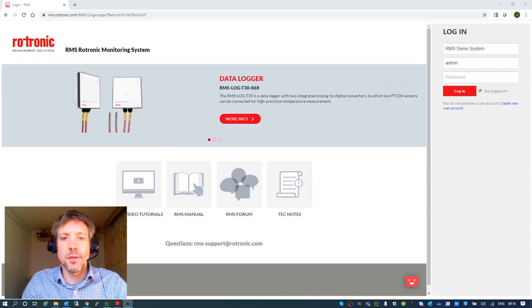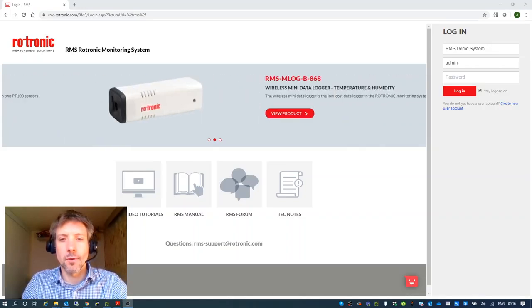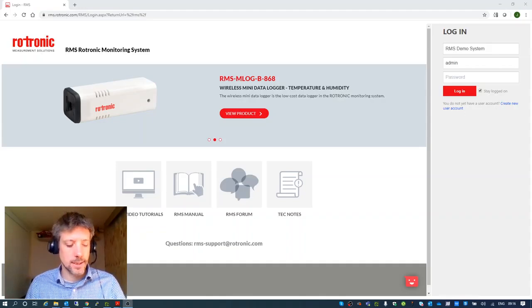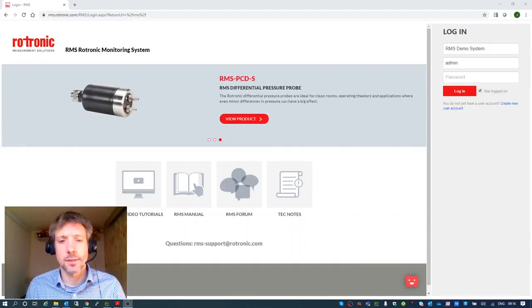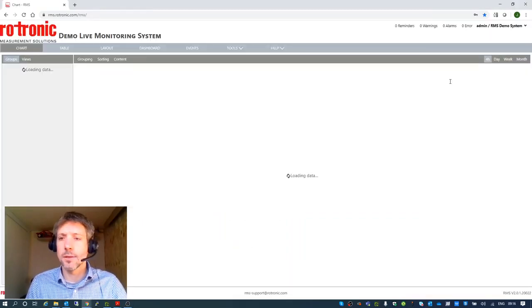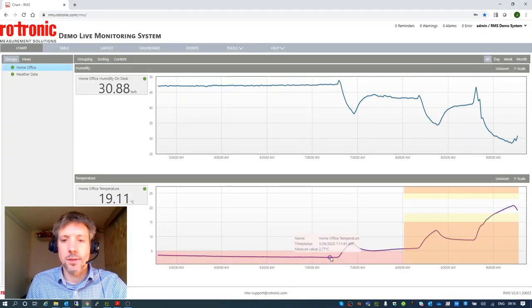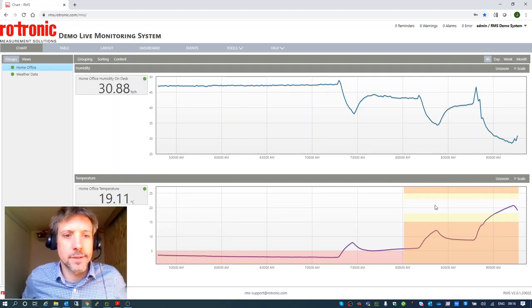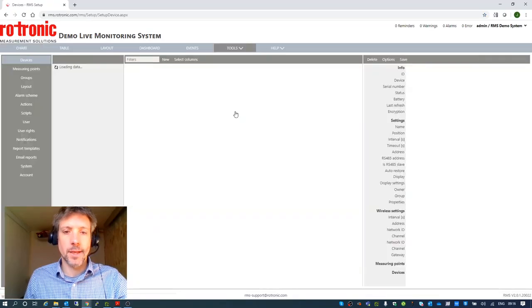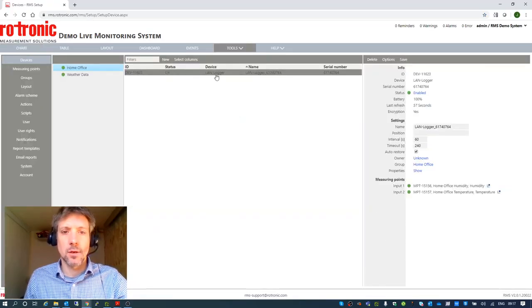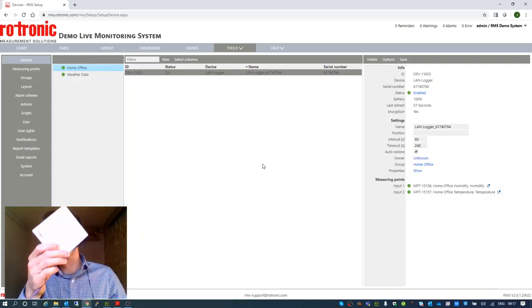So we're going to continue our series of webinars on the Rotronic Monitoring System RMS, and today we've been using a LAN device, and today I wanted to demonstrate how we add wireless devices to the system. So here we are, let's log in to our demo account, and once again we can see a cold night, and heating is coming on and warming up the home office here. So yes, this is a LAN device, and if we want to add a wireless device, we go through to Tools and Setup here. We can see our LAN logger listed here. But to add wireless, we need to add first of all a LAN gateway.